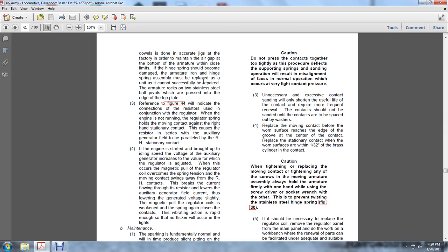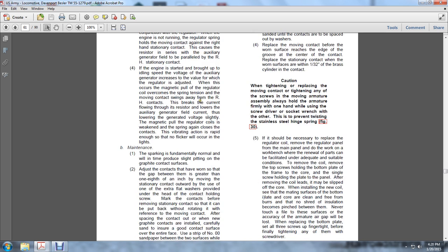If the engine is started and brought up to idle speed, the auxiliary generator voltage increases. The value of the regulator is adjusted for when that occurs. The magnetic pull of the regulator coil overcomes the spring tension and the moving contact swings away from the RH contacts. The current then flows through the resistor and lowers the auxiliary generator field current. This lowers the generator voltage slightly. The magnetic voltage regulator coil weakens, the spring again closes the contact, and the vibrating is rapid enough that no flickering will occur in the lights.